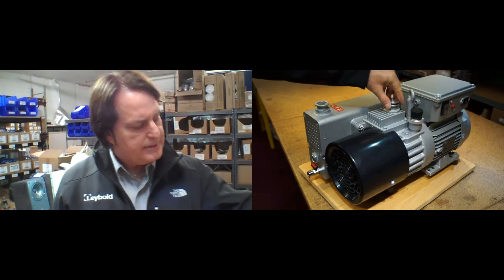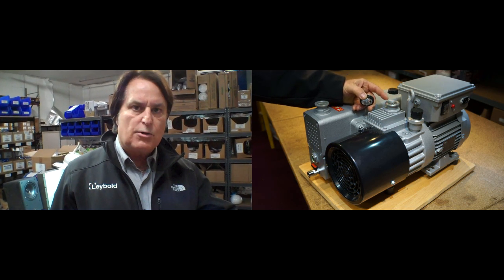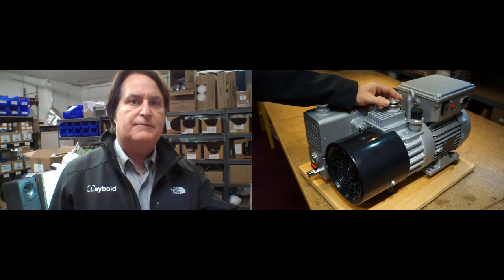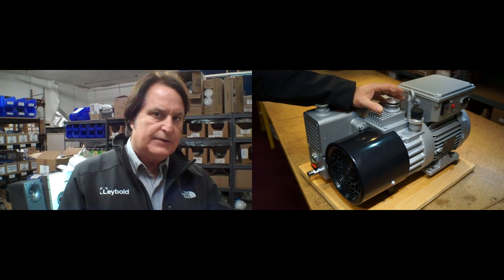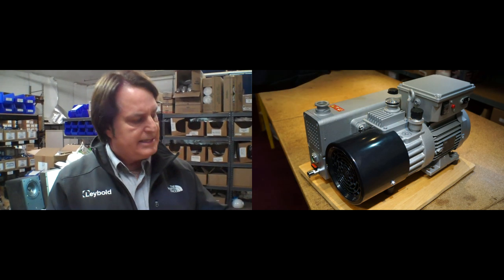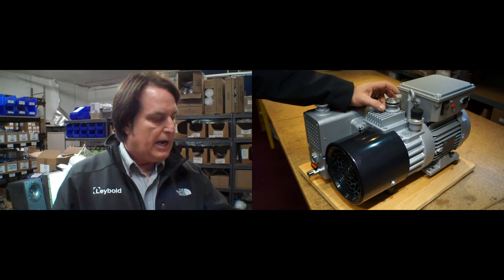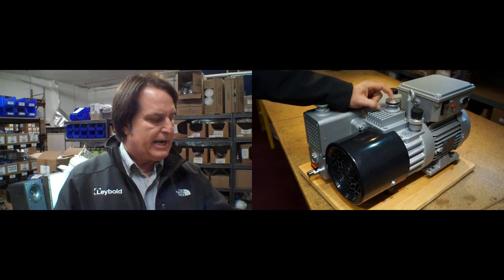On the inlet side, this is a KF25. We have an adapter that goes from KF25 to 3/4-inch JIC so you can hook it up to your Harvest Right hoses. Also behind this plate is what we call an anti-suckback valve. When you shut the pump off, it seals the inlet so you won't get any backstream of oil into the tube. You've seen on certain pumps where you turn the pump off and all of a sudden you see a nice rise of oil in the tube — certainly concerning. But with the Leybold pump you have a really industrial, time-tested anti-suckback valve.